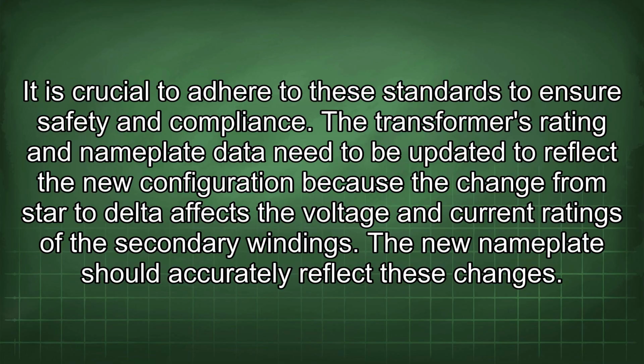The transformer's rating and nameplate data need to be updated to reflect the new configuration because the change from star to delta affects the voltage and current ratings of the secondary windings. The new nameplate should accurately reflect these changes.